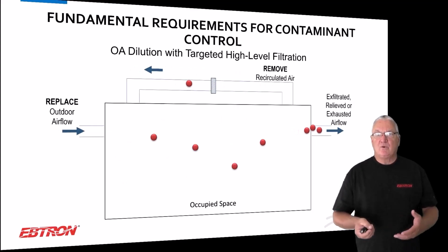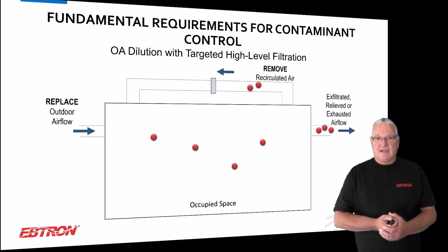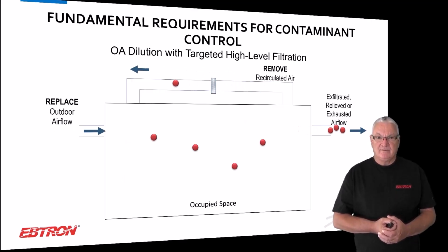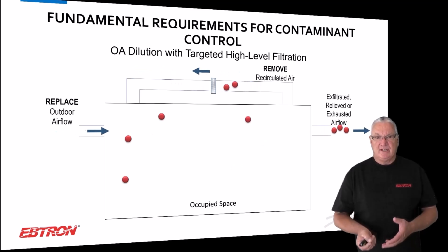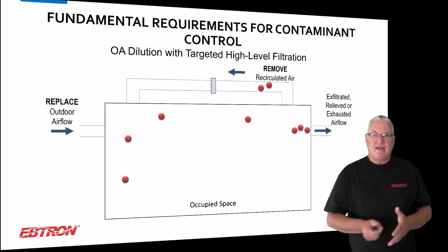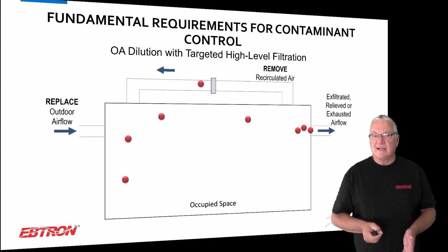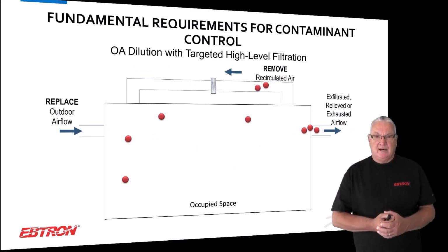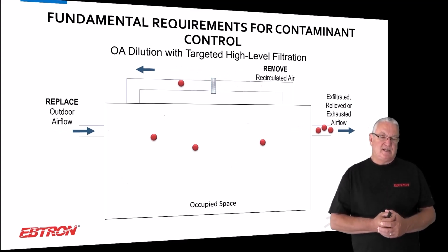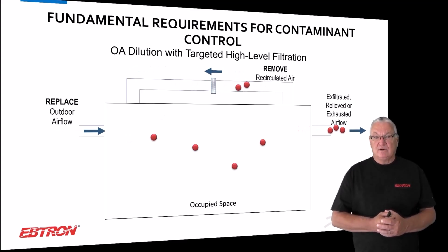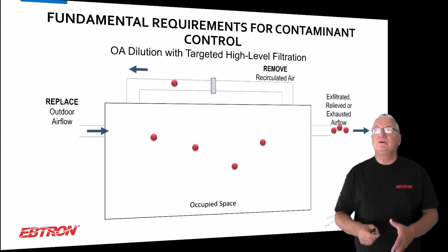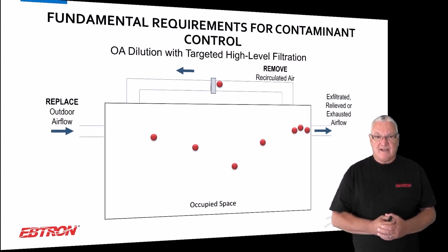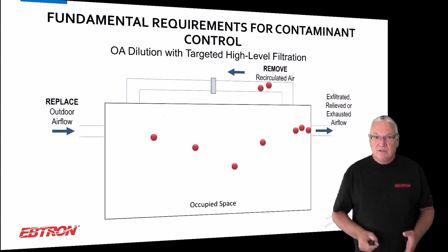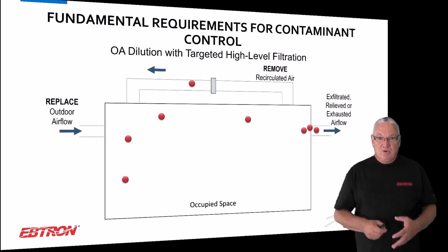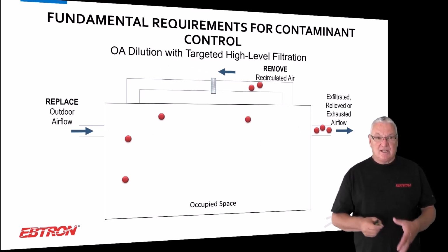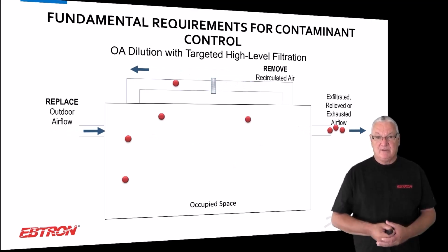All right. So the fundamental requirements for contaminant control in healthcare facilities is going to be a combination of room air changes for filtration and outdoor air changes for dilution. That doesn't mean you can't do anything else in addition to that. I'm not saying that, but I'm saying these are the fundamentals. And I do a lot of work in non-healthcare facilities, and I find that a lot of folks are ignoring the fundamentals, trying everything else they can do for air quality, but forgetting the fundamentals. Fundamentally, this is what we have to do. Okay, we have to remove the contaminants through filtration and dilute the contaminants with outdoor air. Okay, that's just going to be the way it is.